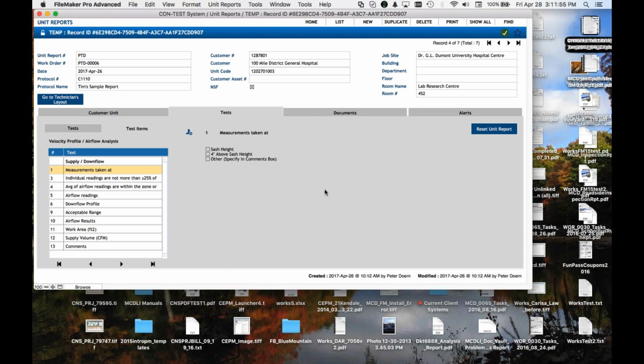Okay. That's very helpful because when we're demoing with Tim, there's one guy in a room with 2 people, and we're walking and doing everything step by step, and he's showing us all the procedures. It didn't occur to me that would be the case, but I think Tim was kind of in training mode for you to say, okay, this is how we do it. But when you've got 2 or 3 technicians on site, or even one technician doing more than one hood, he's not in training mode. He's doing, you know what, I'm going to do all the leak tests first, and then I'll do all the velocity readings, and then I'll do the smoke test, and then I'm out of here.